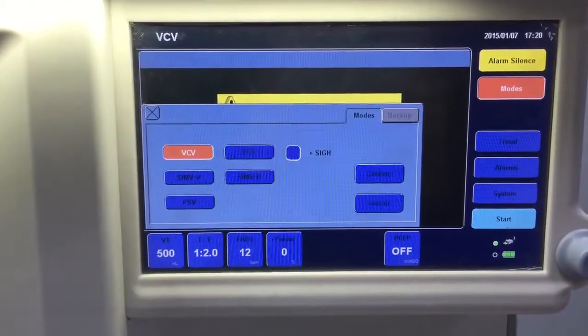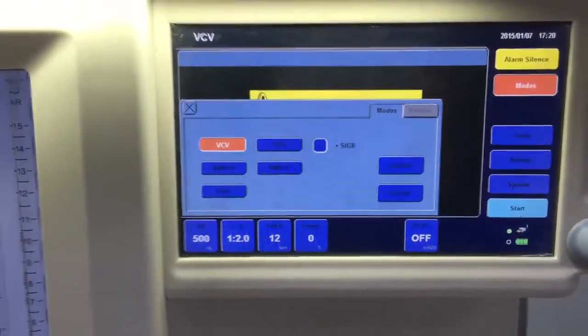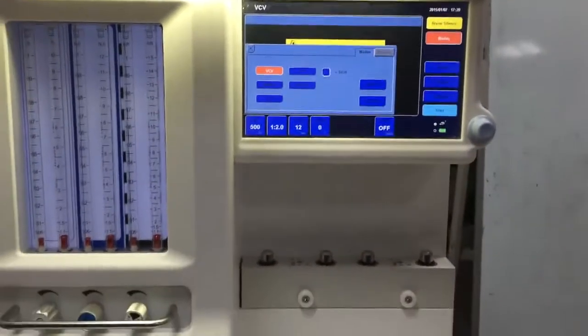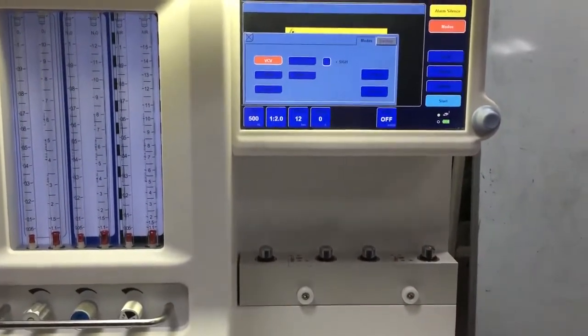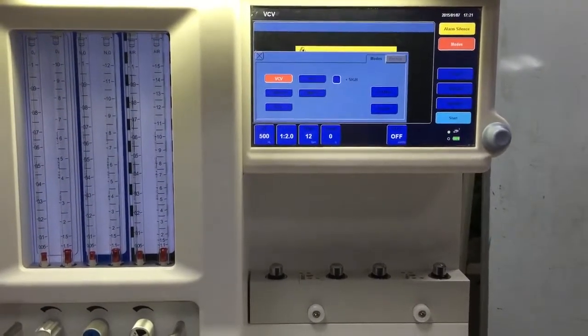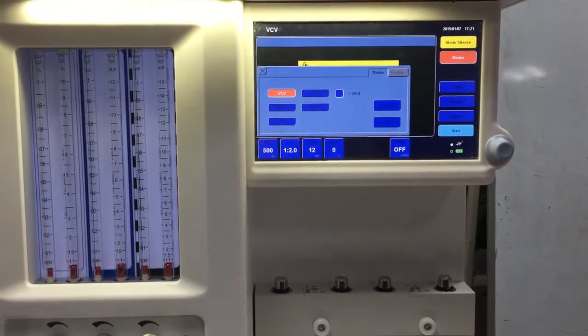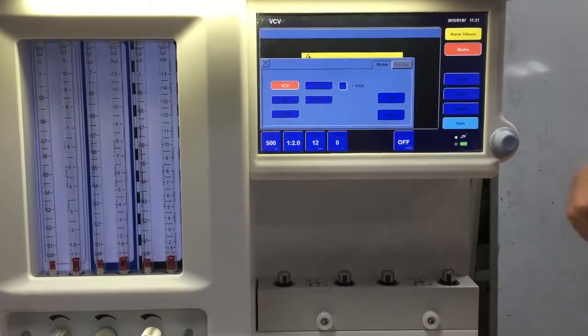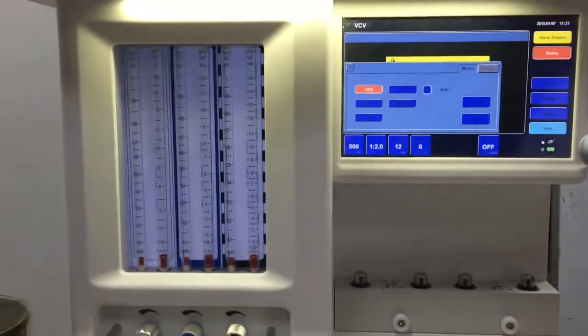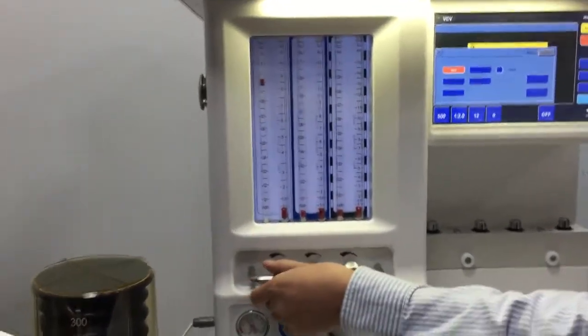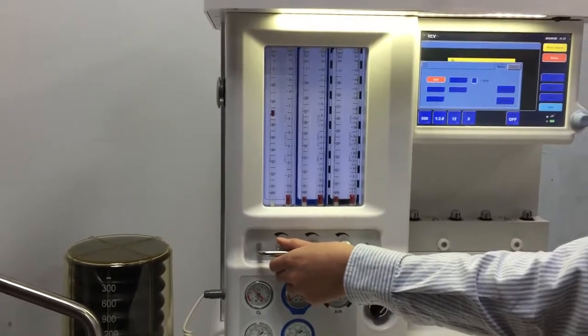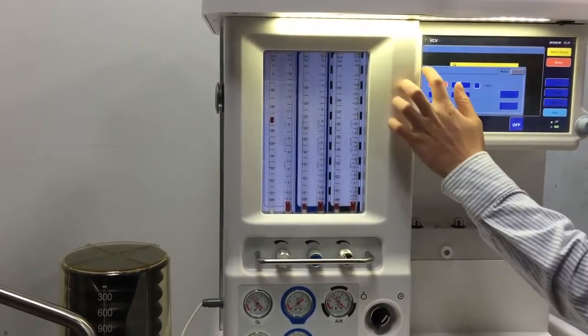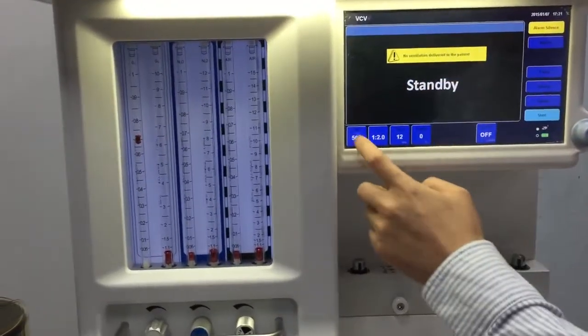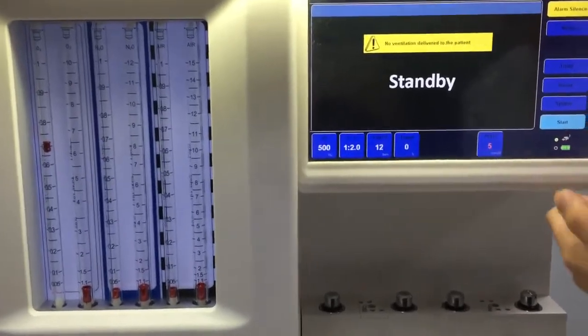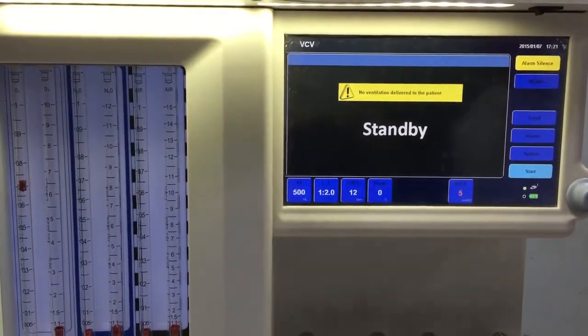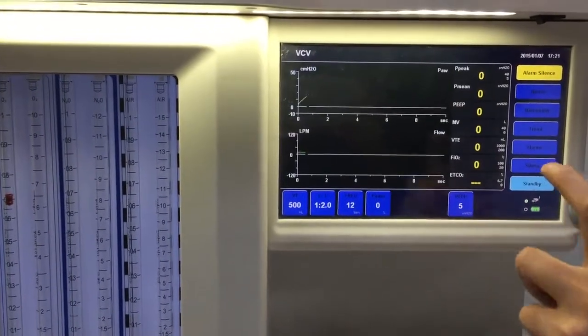Okay, now we are ready for operation. Of course we need a vaporizer if we have one. The vaporizer mounting manifold is standard Selectatec compatible, and we can also offer a Dräger plug-in with 2 vaporizers with an interlock system for safety. We need a low flow rate, maybe 600 milliliters per minute, and then we select volume control, confirm, and set all the parameters we need, such as 5 PEEP. The bellows is filled already, so we can start ventilation.